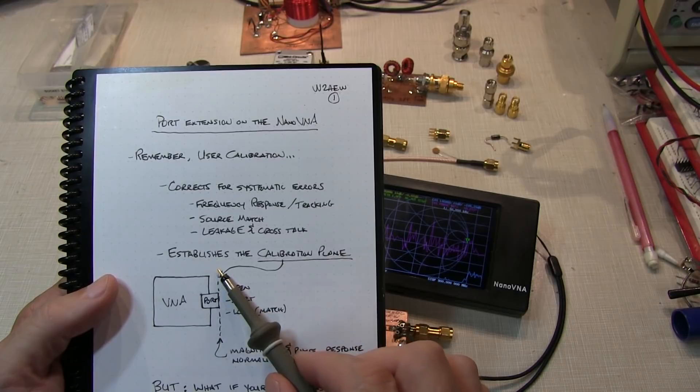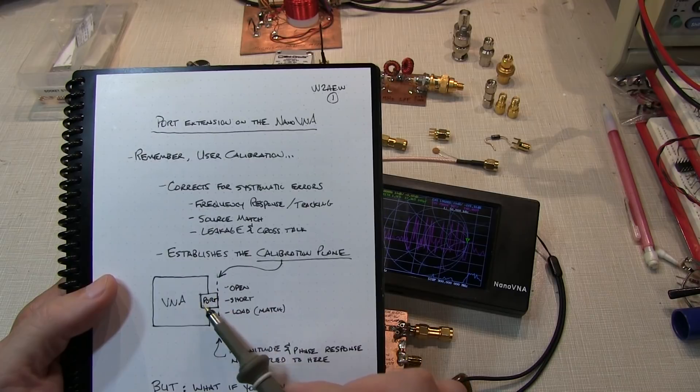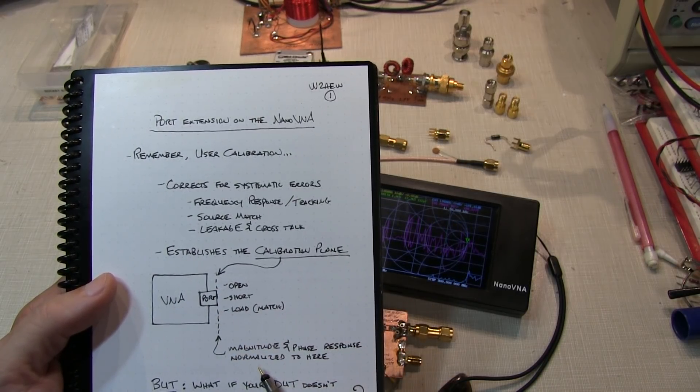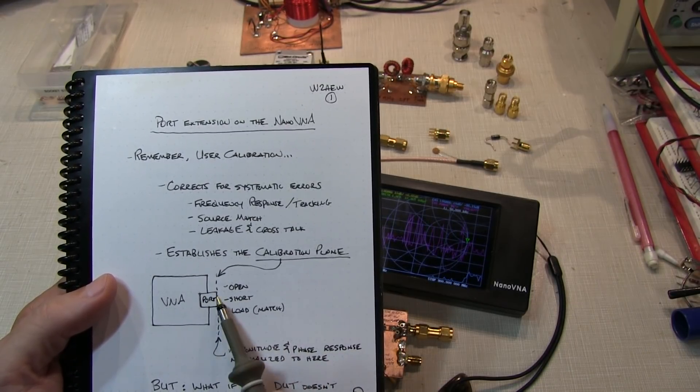And this is essentially the plane where you attach your open, short, and load when doing, in this case, a single port calibration. And what that does is it makes sure that the magnitude and phase of the response is normalized to that point so that we're only measuring the effect of magnitude and phase of the device connected at this location.